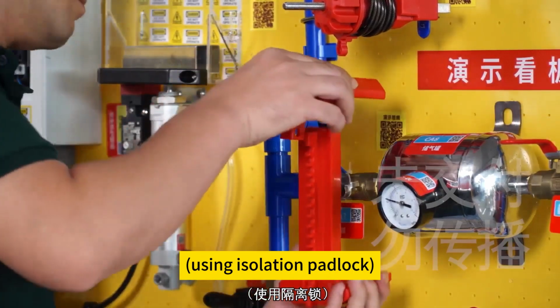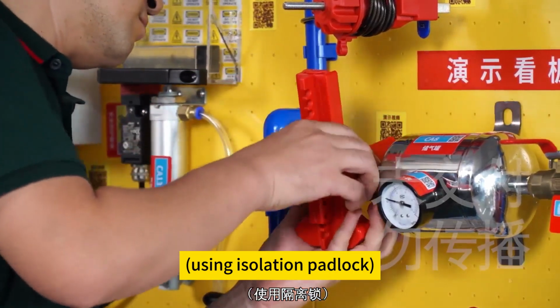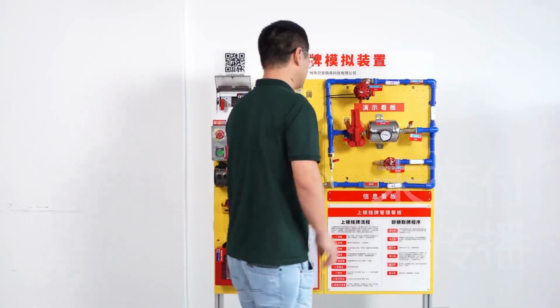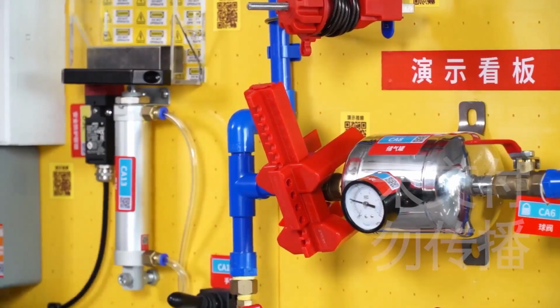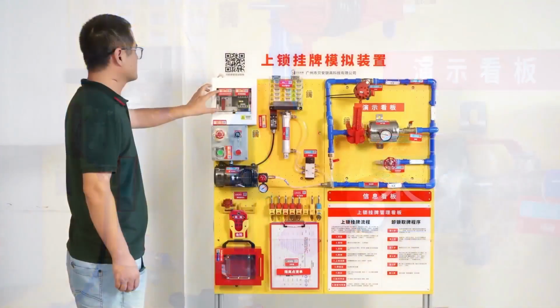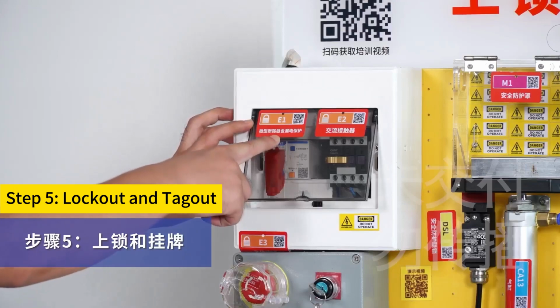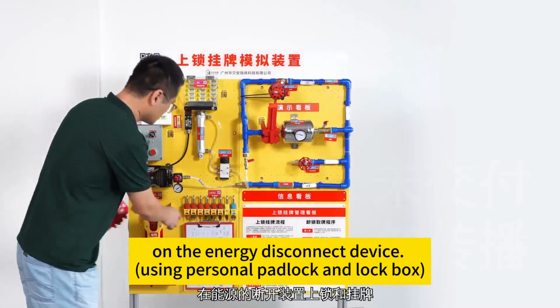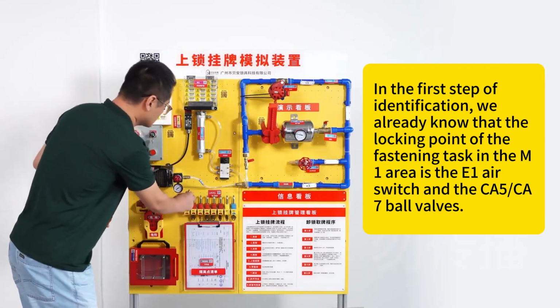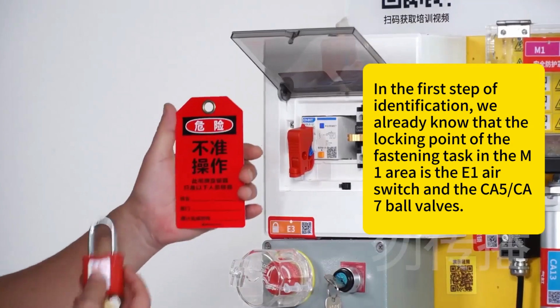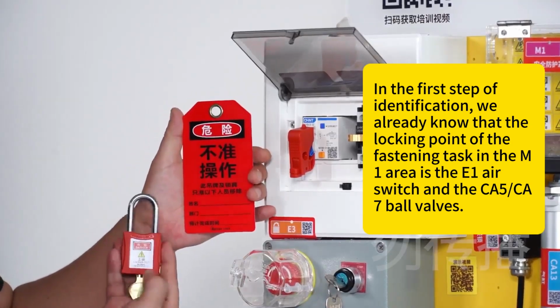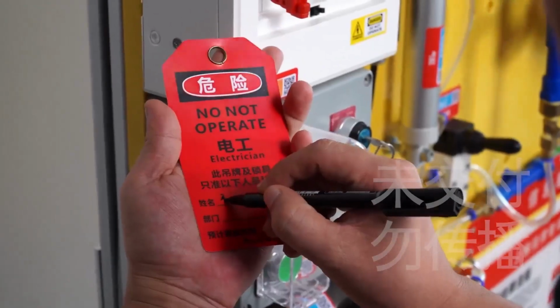Using isolation padlock. Step 5. Lockout and tagout. On the energy disconnect device, use a personal padlock and lockbox. In the first step of identification, we already know that the locking points of the fastening task in the M1 area are the E1 air switch and the CA5/CA7 ball valves.